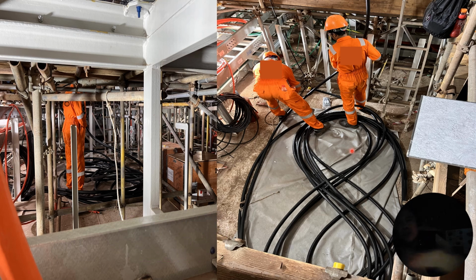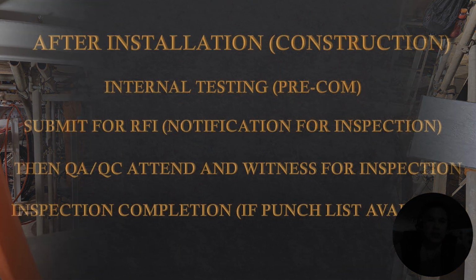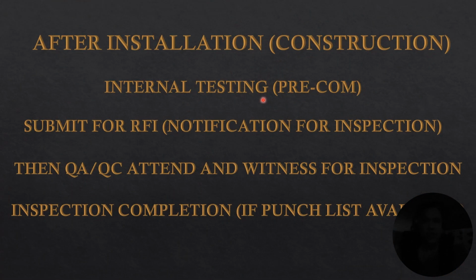So when you run your cable, you do the cable pulling and go towards the equipment, so there's no stressing of the cable and no damaging of the cable. All right. So that is the important thing that the construction team needs to know about this, and this will be supervised by the supervisor, foreman, and the engineers as well. All right. So after that, everything is in place and internal testing is completed. After the installation, the construction is completed, and then internal testing.